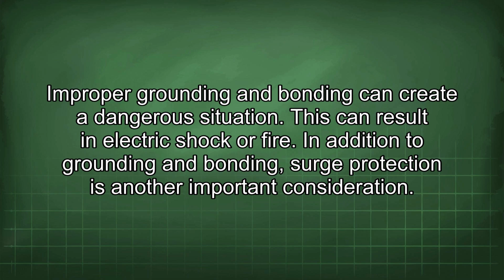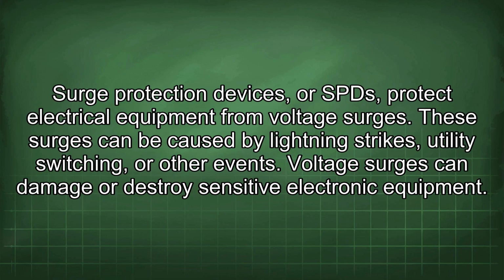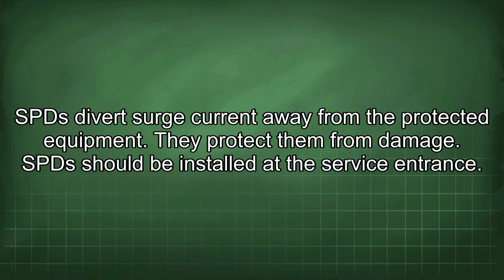In addition to grounding and bonding, surge protection is another important consideration. Surge protection devices, or SPDs, protect electrical equipment from voltage surges. These surges can be caused by lightning strikes, utility switching, or other events. Voltage surges can damage or destroy sensitive electronic equipment. SPDs divert surge current away from the protected equipment. They protect them from damage.